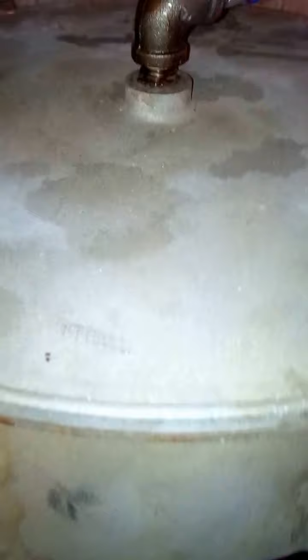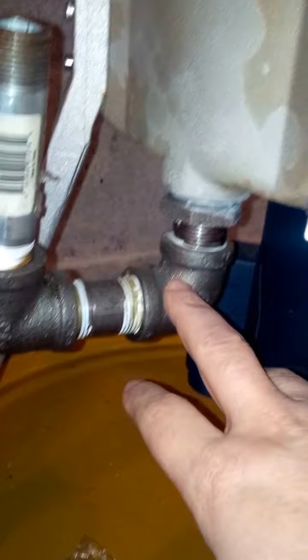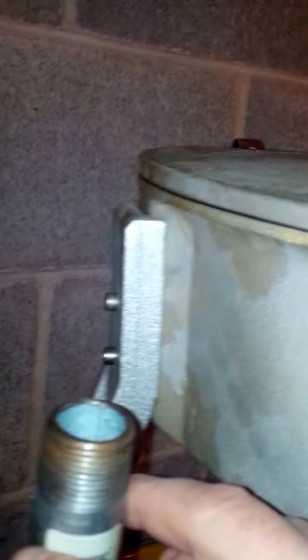What happens is the dirt and any contaminants stick to the side of the wall, but the oil keeps flowing freely up into the top of the centrifuge, and it spins out. Then it comes out the bottom here, down through this tube - this is the clean oil. This here is just a vent tube, and I don't know if you can see it or not, but there's actually steam that comes out of this vent tube.